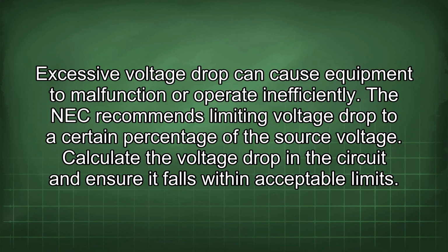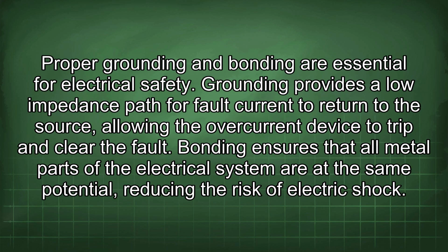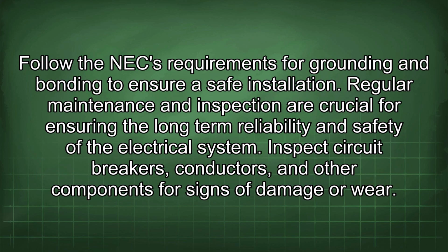The NEC recommends limiting voltage drop to a certain percentage of the source voltage. Calculate the voltage drop in the circuit and ensure it falls within acceptable limits. Proper grounding and bonding are essential for electrical safety. Grounding provides a low impedance path for fault current to return to the source, allowing the overcurrent device to trip and clear the fault. Bonding ensures that all metal parts of the electrical system are at the same potential, reducing the risk of electric shock. Follow the NEC requirements for grounding and bonding to ensure a safe installation.